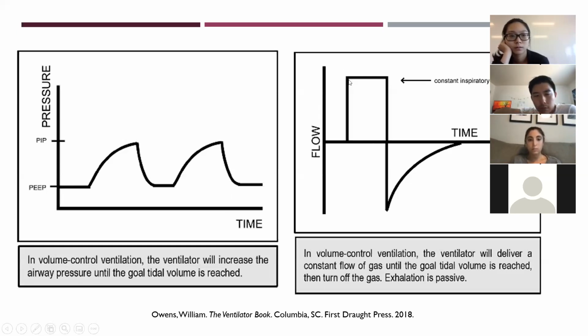During inspiration, your machine will deliver this flow of air to get your tidal volume. And throughout the course of inspiration, this is going to be a constant flow of air. The source I got this from described it like drinking from a fire hydrant. So in some ways, this can be uncomfortable for the patient because as soon as they trigger a breath or want to breathe, they literally get a blast of air for the entire time of inspiration. So keep this in mind. We'll compare it to other modes later in this lecture. But after that, you have passive exhalation.